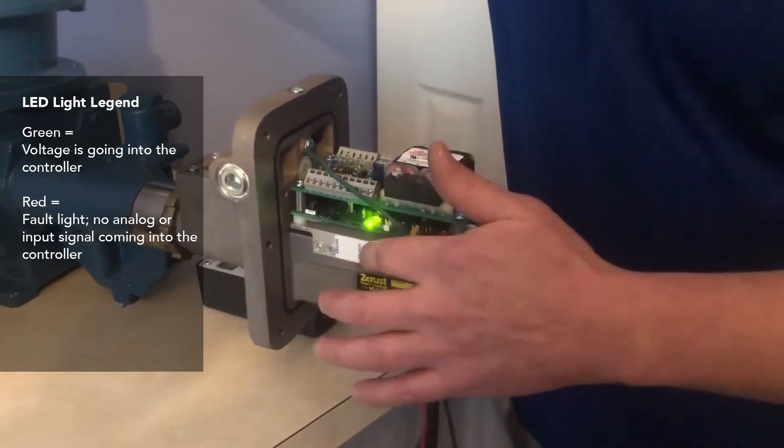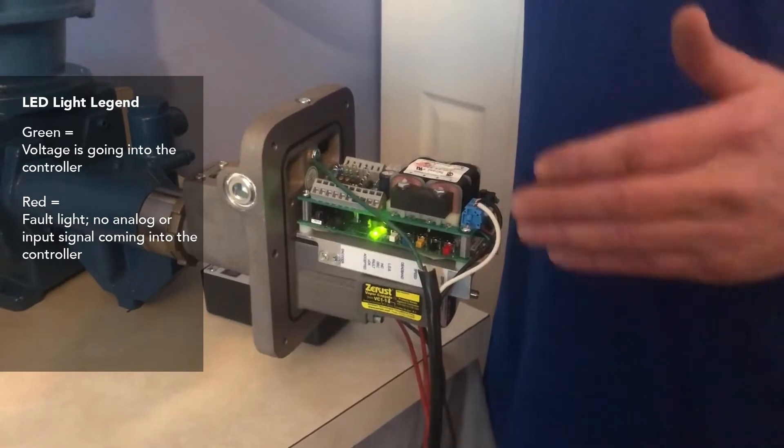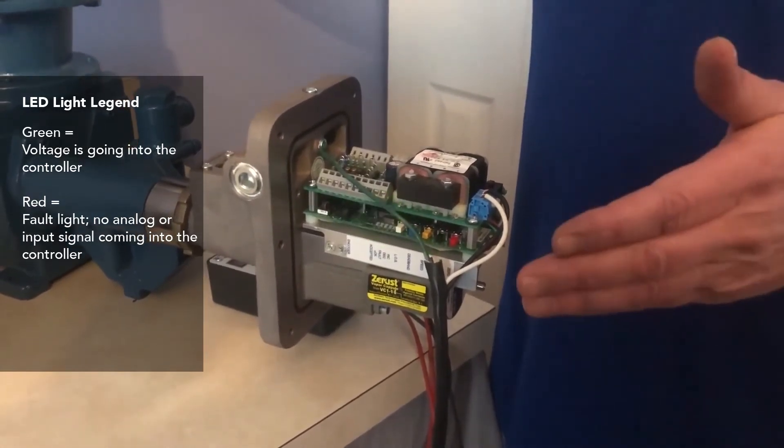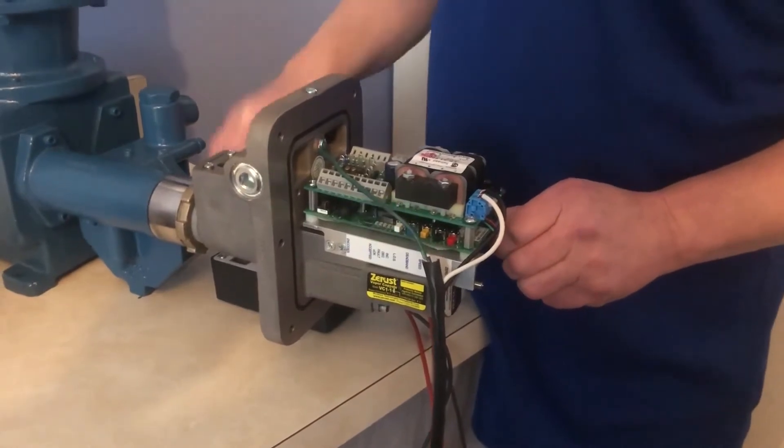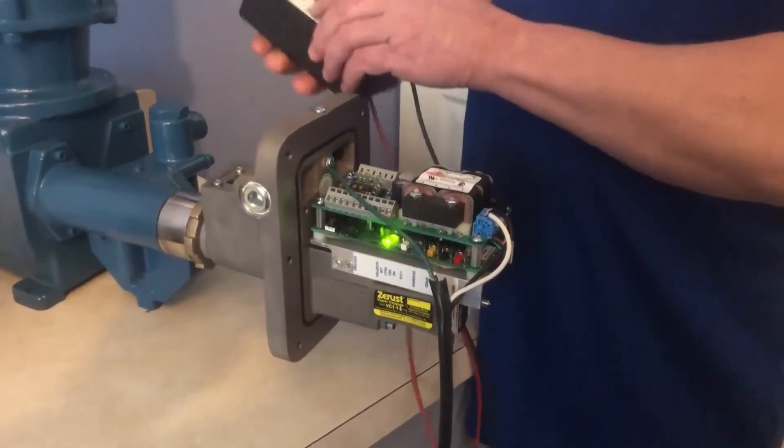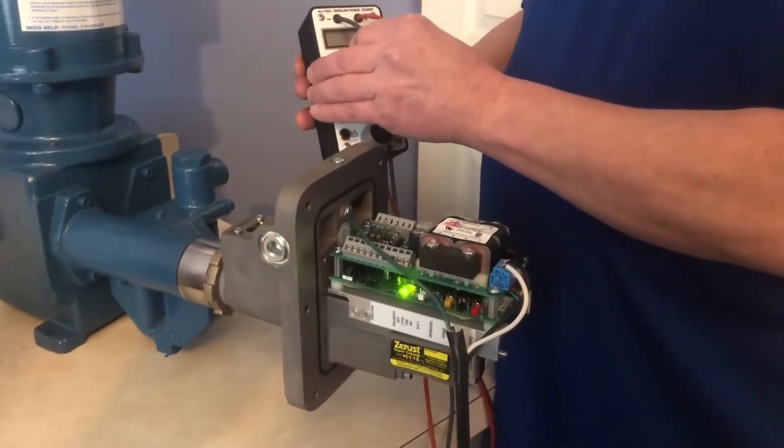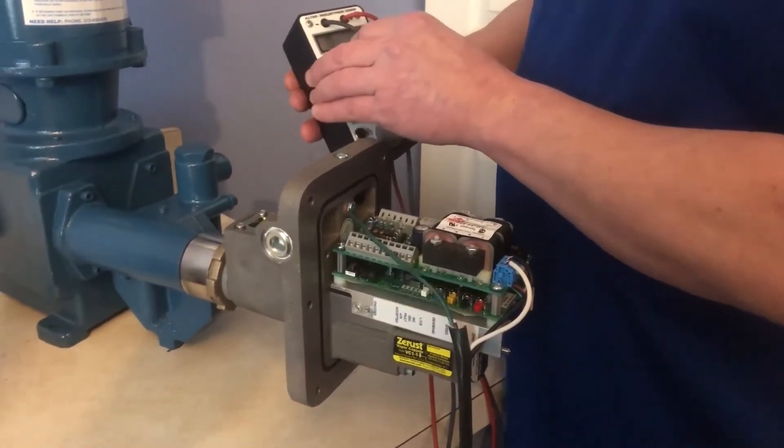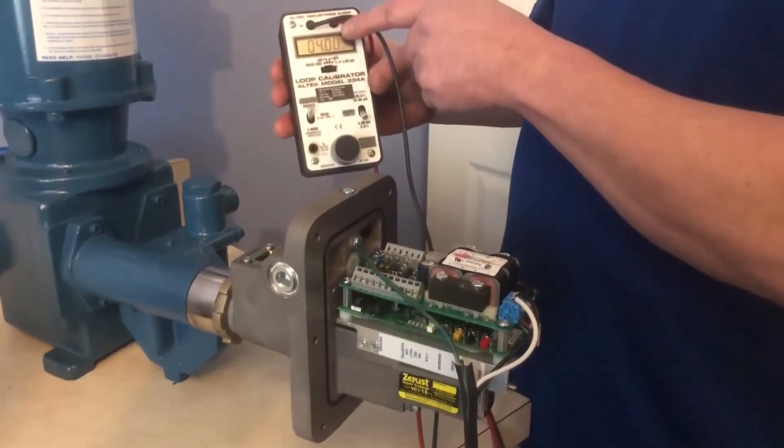The red LED is a fault light, which typically means there's no analog or input signal coming into the controller. Now, when I get the simulator out and simulate a signal, that red light should go off. The red light went off. And we have a four milliamp signal.